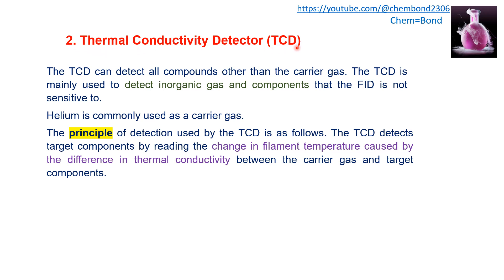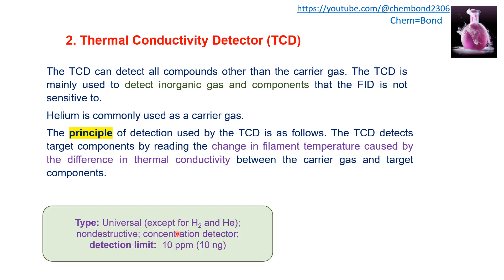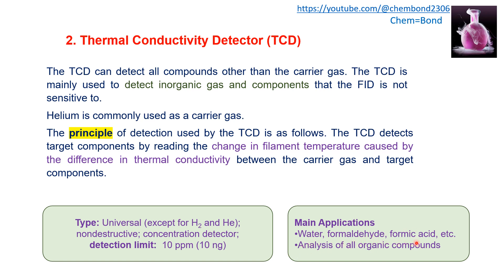The second detector is the thermal conductivity detector (TCD). TCD can detect all compounds other than the carrier gas. It is mainly used to detect inorganic gases and components that FID is not sensitive to, such as compounds FID cannot detect. The principle of TCD is that it detects target compounds by reading a change in filament temperature caused by the difference in thermal conductivity between the carrier gas and the target component. It is a universal, non-destructive, concentration detector with a detection limit of 10 ppm. Main applications include water, formaldehyde, formic acid analysis, and analysis of all other organic compounds.